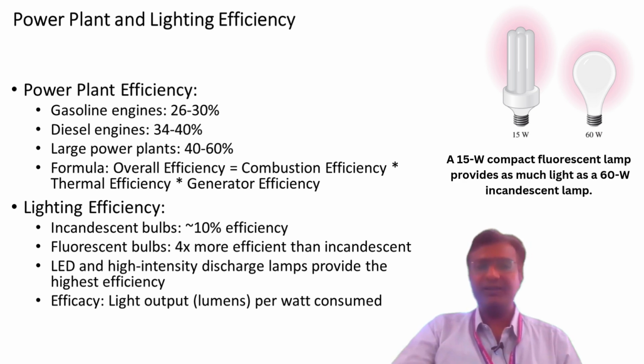These large power plants achieve efficiency between 40 to 60%, not beyond that. The formula used to calculate overall efficiency is combustion efficiency multiplied by thermal efficiency multiplied by generator efficiency. This shows the overall efficiency depends on how well each stage of energy conversion performs. Combustion efficiency relates to how effectively the fuel is burned, thermal efficiency involves converting heat into mechanical energy, and generator efficiency pertains to converting mechanical energy into electrical energy.